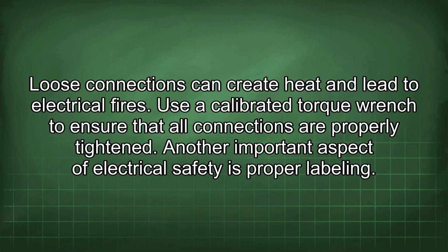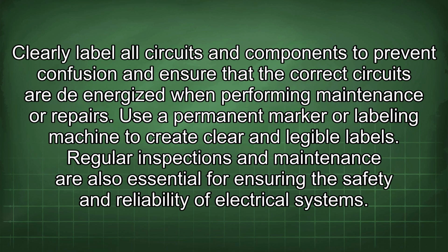Loose connections can create heat and lead to electrical fires. Use a calibrated torque wrench to ensure that all connections are properly tightened. Another important aspect of electrical safety is proper labeling. Clearly label all circuits and components to prevent confusion and ensure that the correct circuits are de-energized when performing maintenance or repairs. Use a permanent marker or labeling machine to create clear and legible labels.